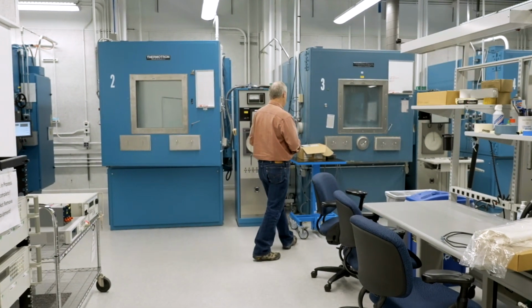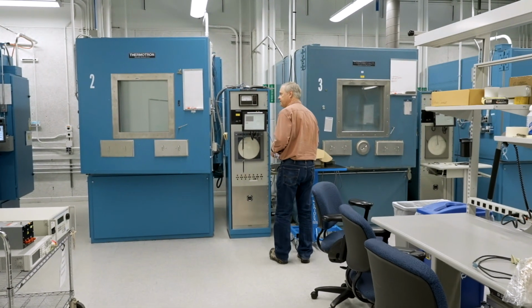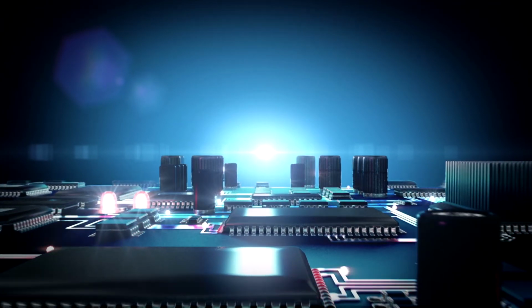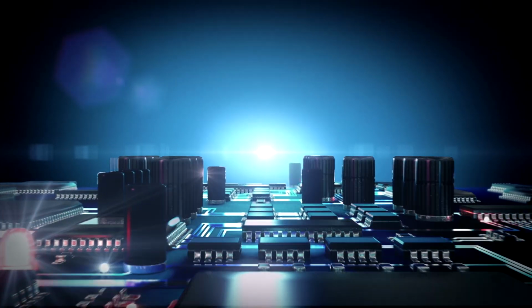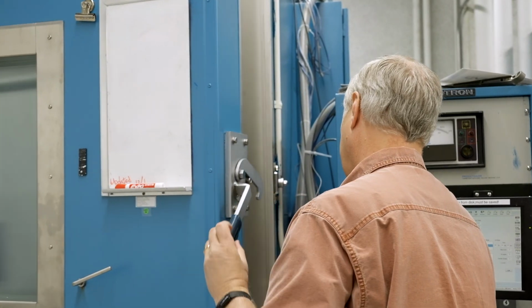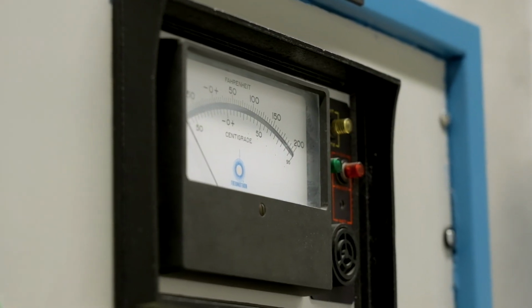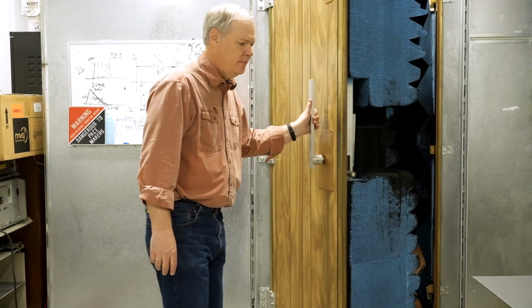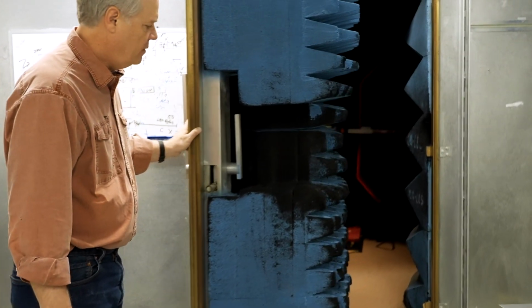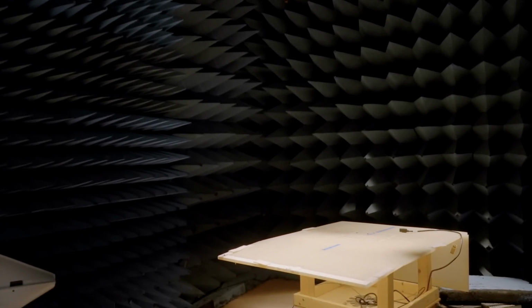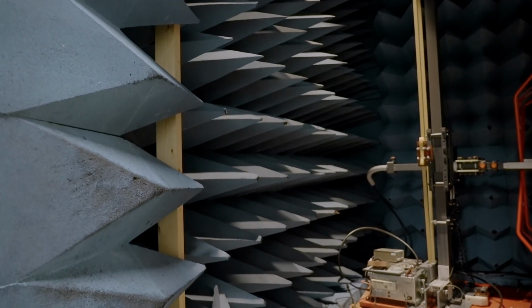We design our equipment to be very stable in hardware, and we do things specifically. We use special materials, and we lay out PC boards in a certain way, and we do a variety of things to make the hardware physically stable as we can. But then, after we do that, we apply a lot of error correction. We do lots of temperature characterization and humidity characterization, and then we apply error corrections to make it even more stable. We have a chamber downstairs that we use to measure the radiated emissions of our products and make sure that they're not too susceptible to other radiation from outside, RF kind of stuff that gets in and messes up your measurements.